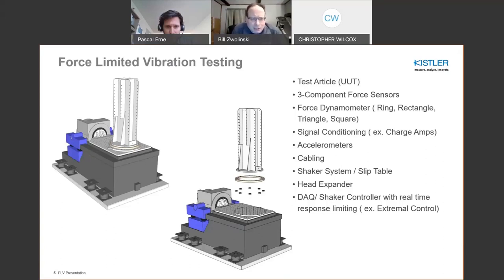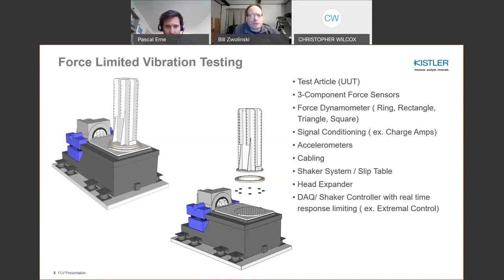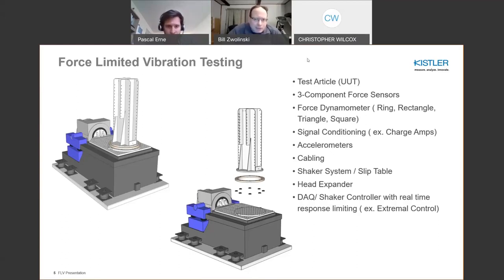As for the force limited vibration test, this rendering shows a system at a customer location: basically a slip table with four sensors mounted on the base and a test article mounted to those four sensors. This is the basic concept — you instrument the interface between the shaker and the unit under test with force sensors to measure the fixed-base resonances during vibration testing.